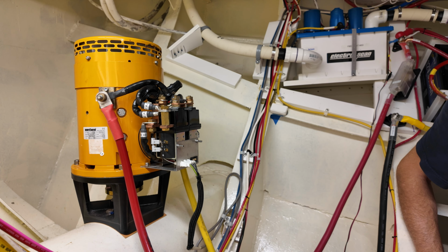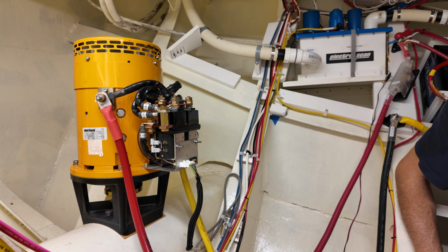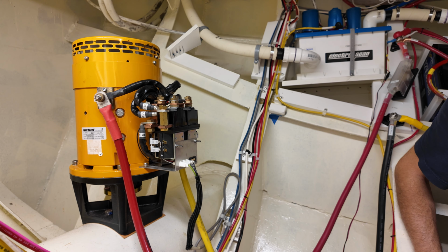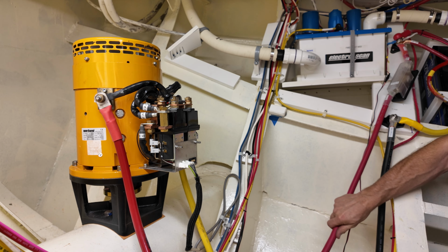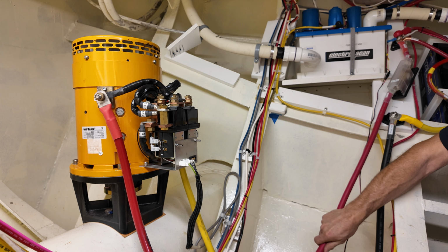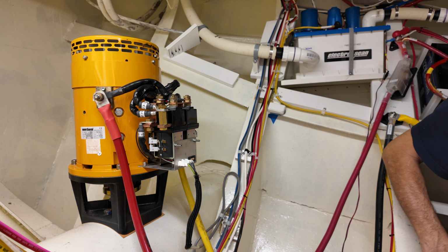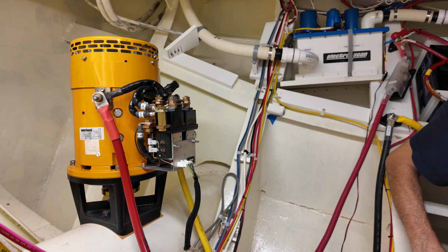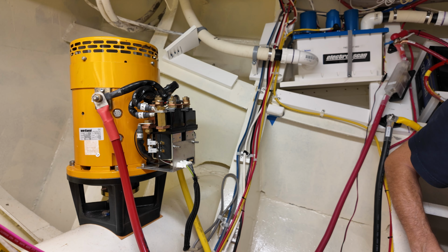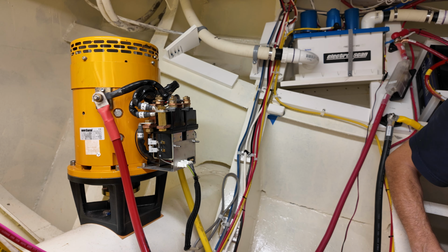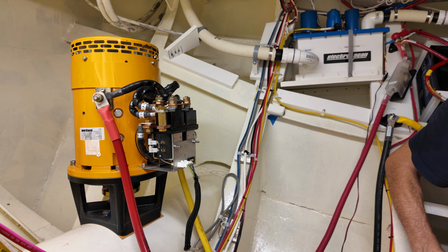Now we need to do all the current measurements and confirm that we need to add 2 more batteries. That seems to have fixed all the running issues. Now I just want to confirm the current coming out of the batteries, and the current going into the motor. We could possibly have issues with the 4 breakers we have on each battery — they could be limiting current or causing extra current to be pulled.